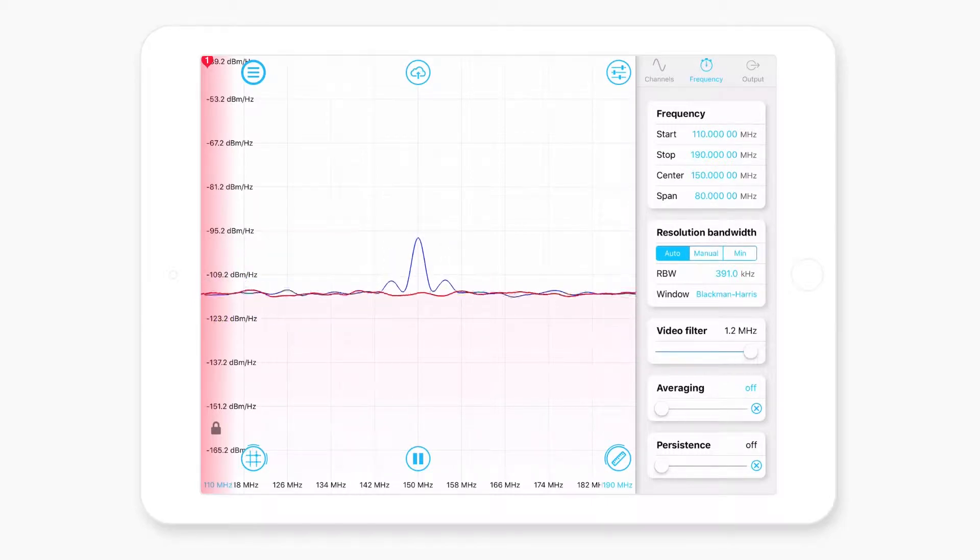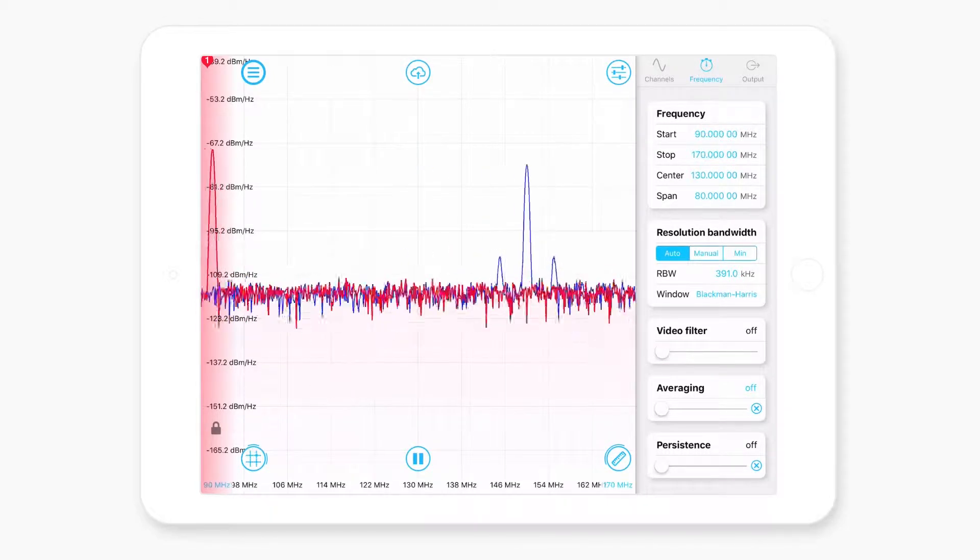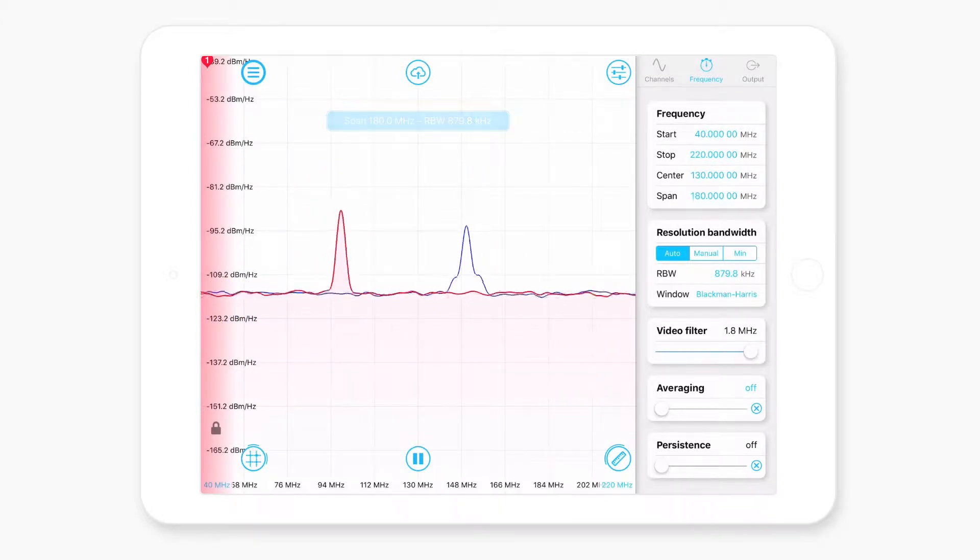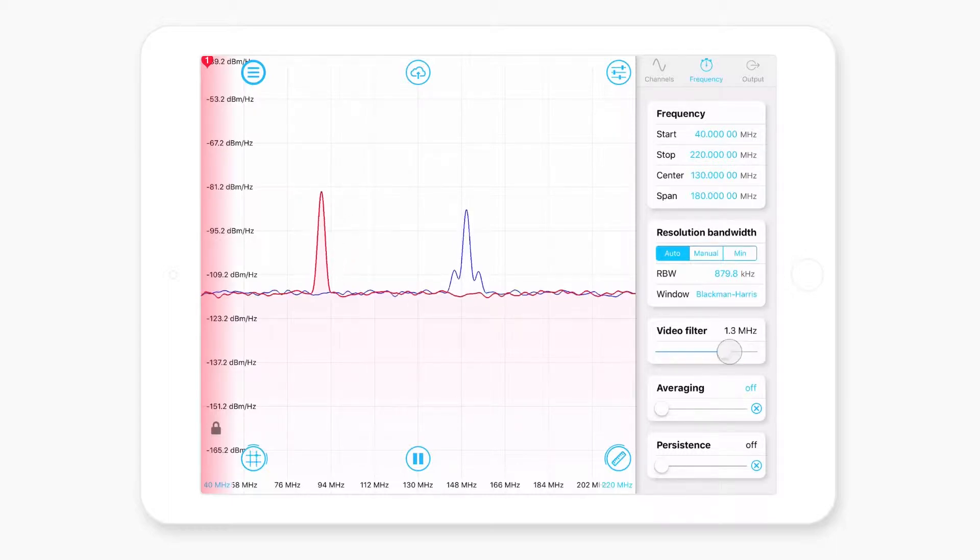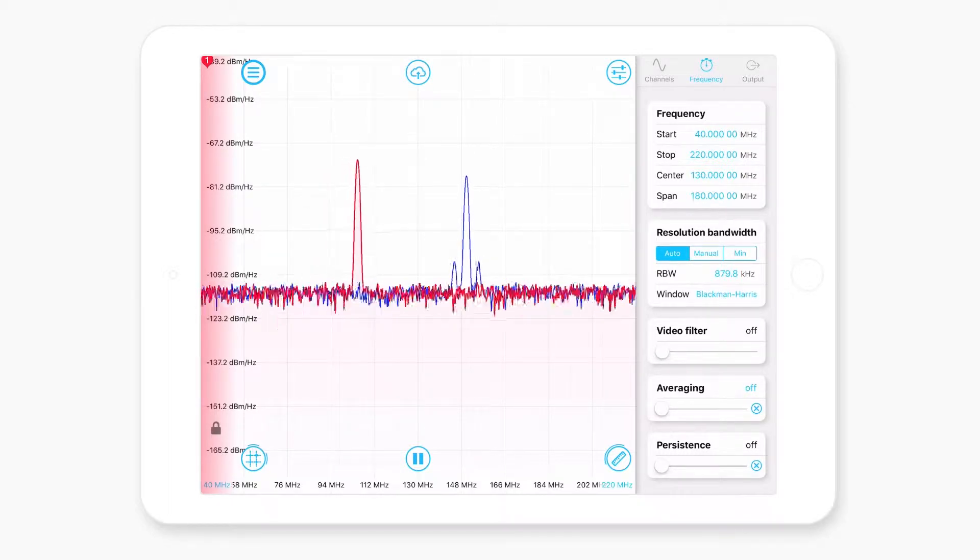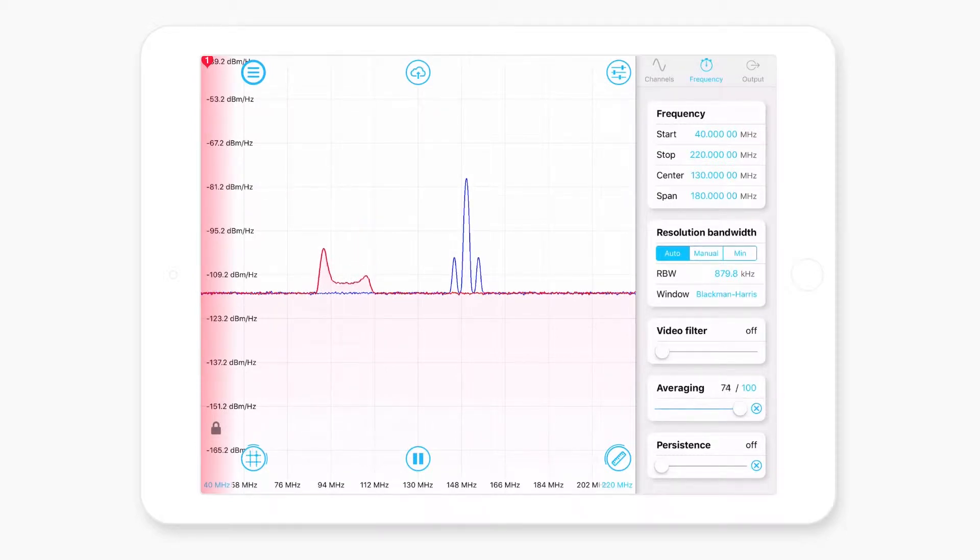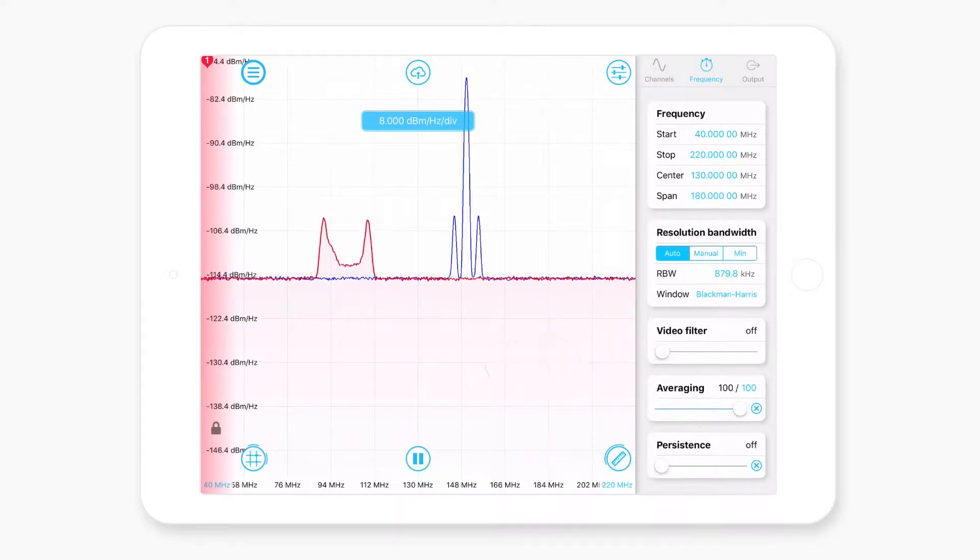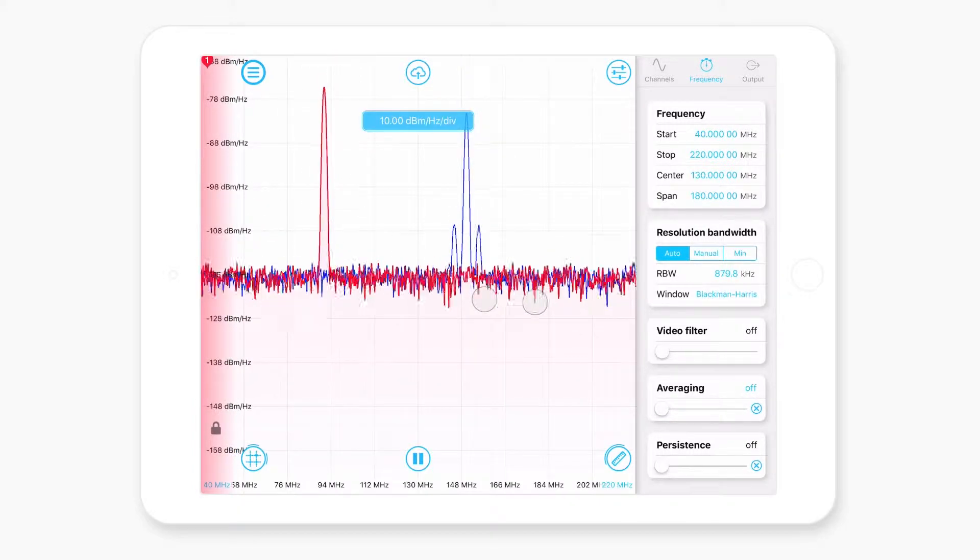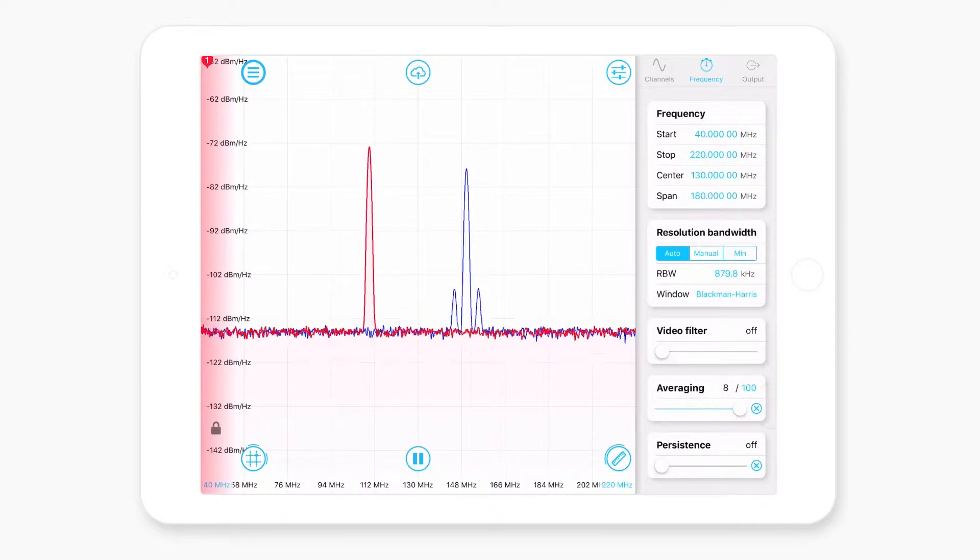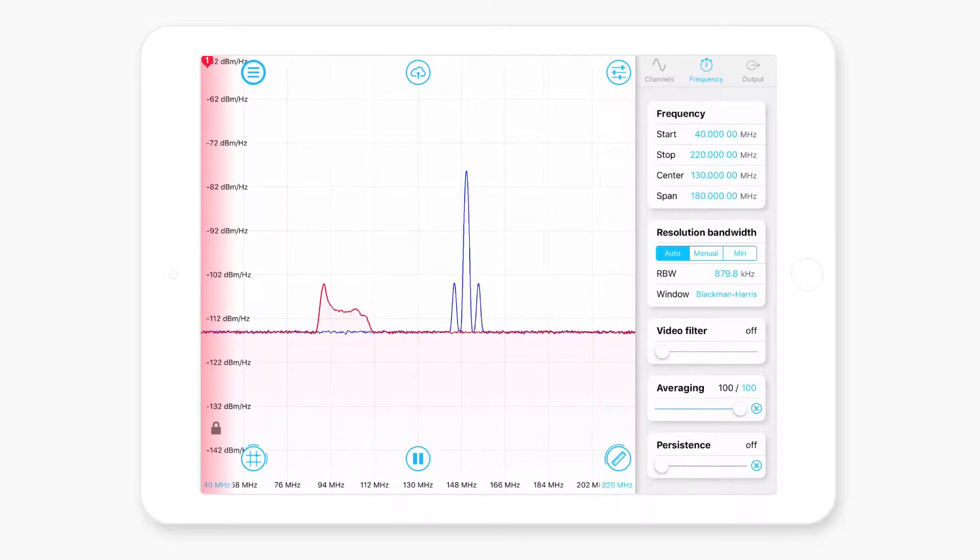You've got a video filter, really not sure what the go with that is. I don't personally ever use it, but I imagine it's just a nice way of smoothing out different features. Averaging is very useful. So if I turn that up, you'll notice that the noise on the bottom here is basically just sort of melts into this single line, whereas if I turn it off, it's quite bubbly and dynamic. So averaging is really handy if you want to essentially reduce the noise and maximize the clarity of the signal that you're observing.